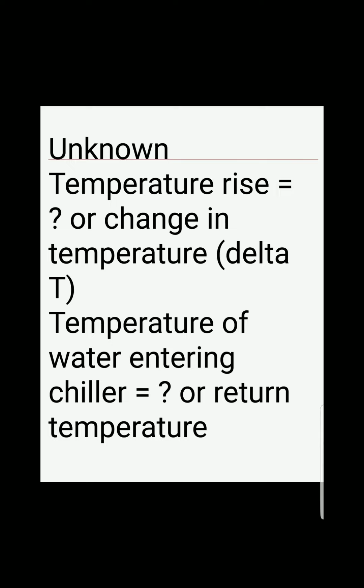So solution. So we solve first for the temperature rise or the delta T. First task is to convert the tons that we are given, tons of capacity, into BTU per hour. So 60 tons, we multiply the conversion factor of 12,000 BTU per hour per ton, and so we get 720,000 BTU per hour capacity.